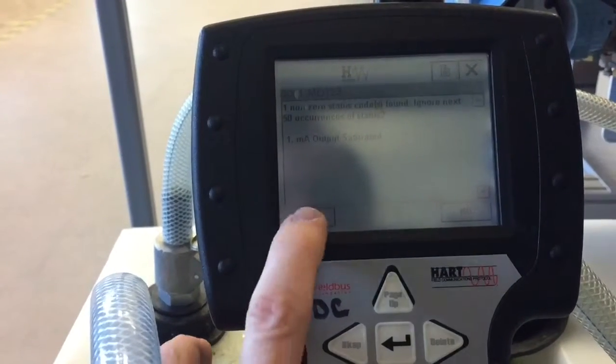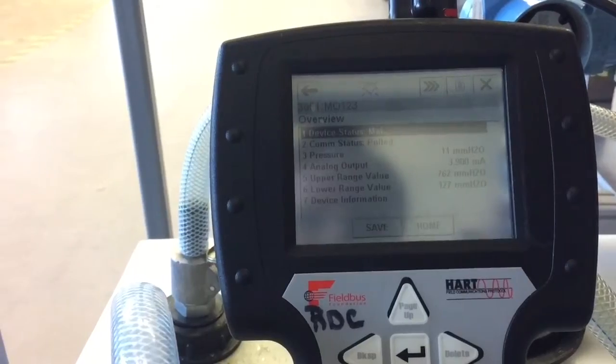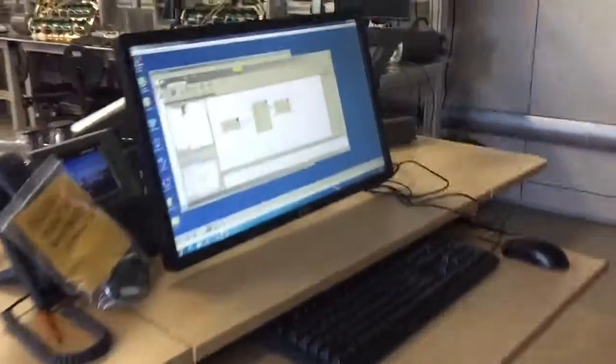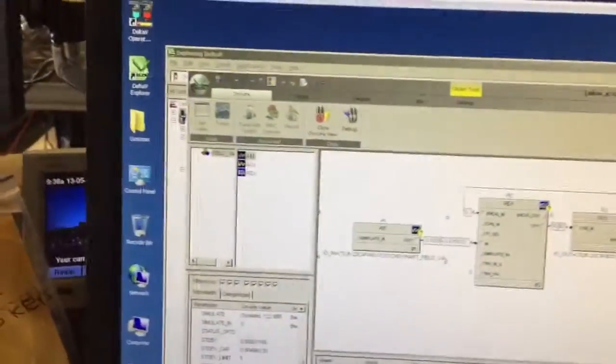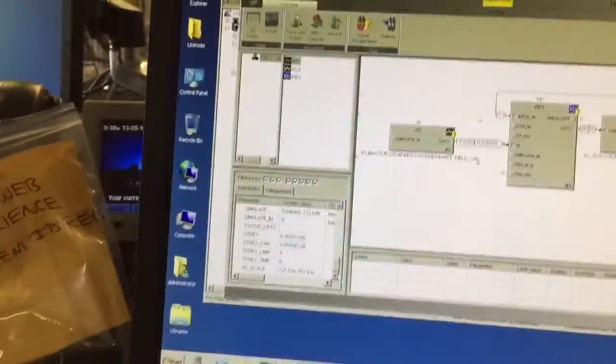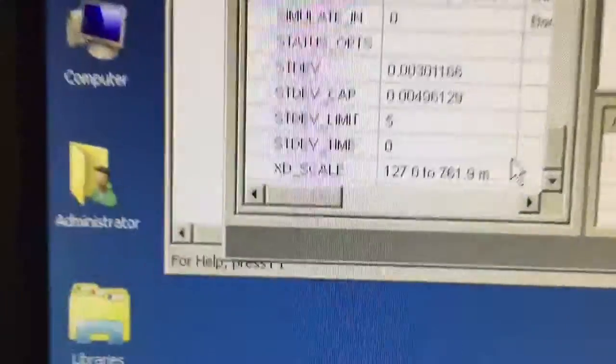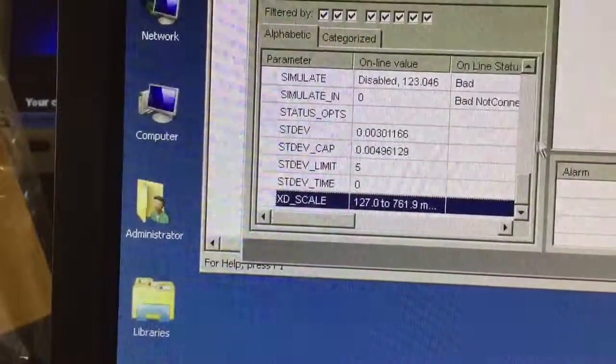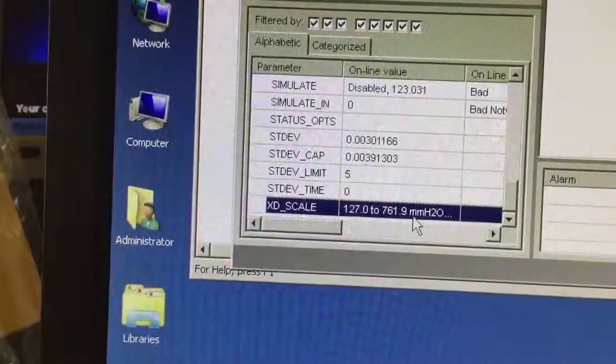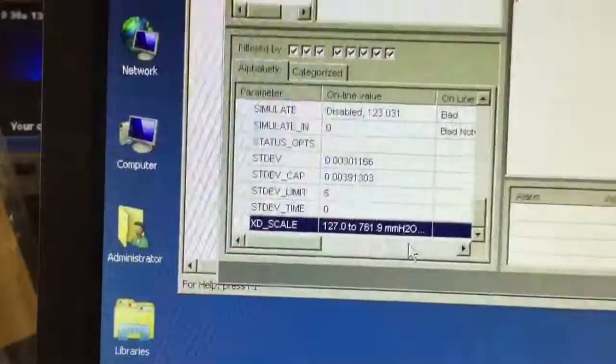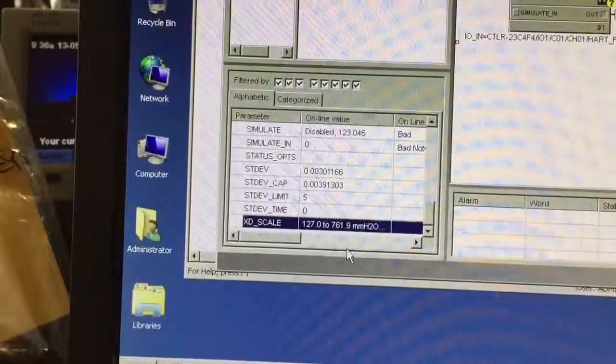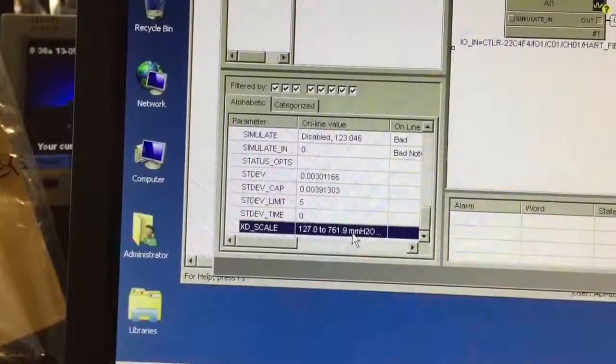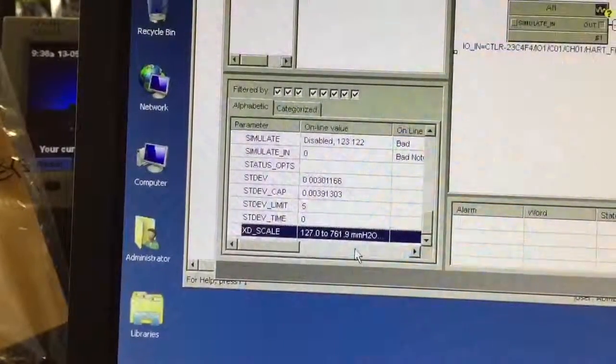Let's look at our DeltaV control system and see if the update was made. If you come over here now, we're online. And you can see right here that our XD scale has been converted to millimeters H2O, and it was reading in inches H2O before 5 to 30. And the corresponding values in millimeters H2O have been updated.